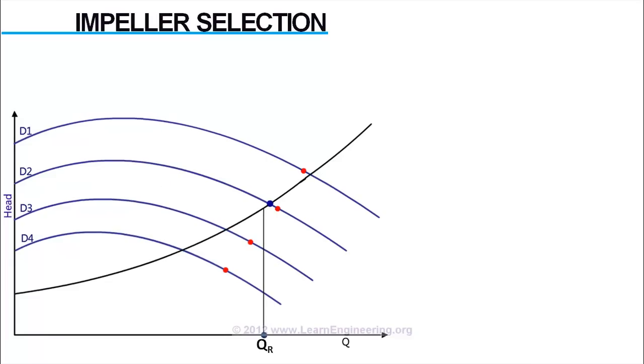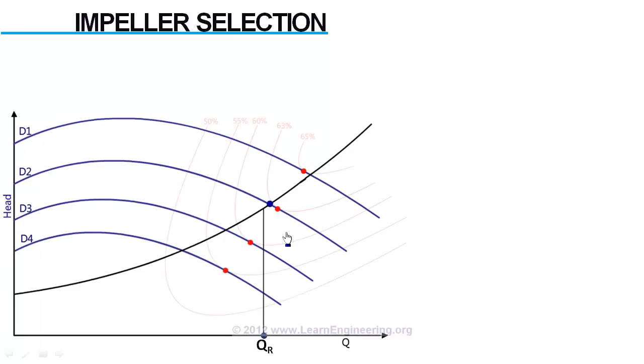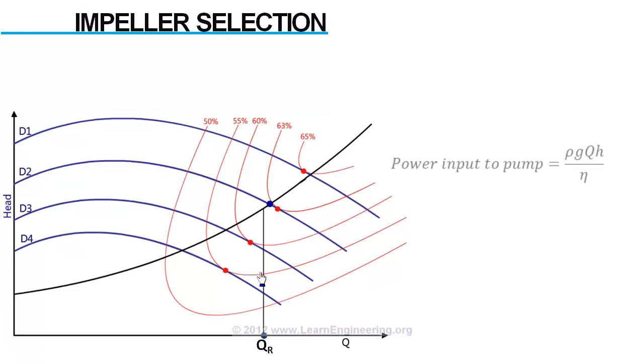In the same graph, we can represent iso-efficiency curves. So, efficiency at the operating condition also can be determined. The required shaft power can be calculated using this equation. This will lead to proper motor selection.